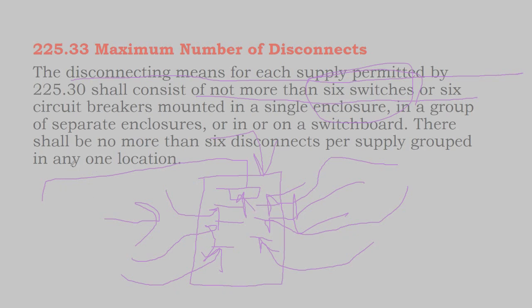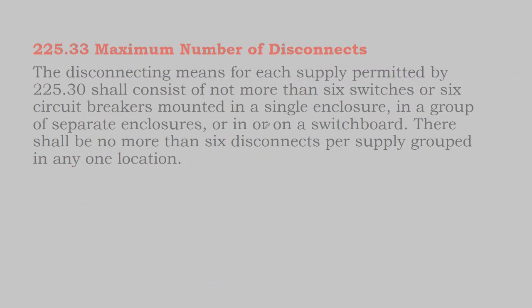Or alternately, you put in a knife switch disconnect with a fuse, and that would serve in lieu of the main breaker. But in either case, you have your main overcurrent protection device and switch where you can flick no more than 6 switches to fully de-energize that supply.